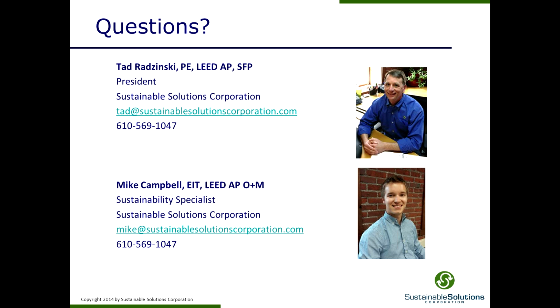We actually did this on an existing building model where we tried to look at the effect of dirty air filters on the energy usage in the building. After doing some research, I came up with an estimate for the change in total static pressure of the system for dirty filters compared to clean filters, and made that change as a parametric run in the model. In eQuest, there's no way that I know of to directly account for older equipment, but you can do some research, come up with assumptions on what the change in efficiency might be, maybe model a 10% loss in efficiency or something to a certain system. You can always model things indirectly like that to come up with an estimate.